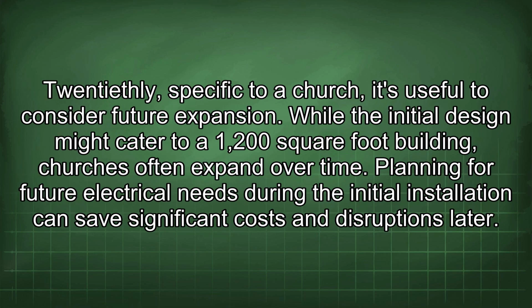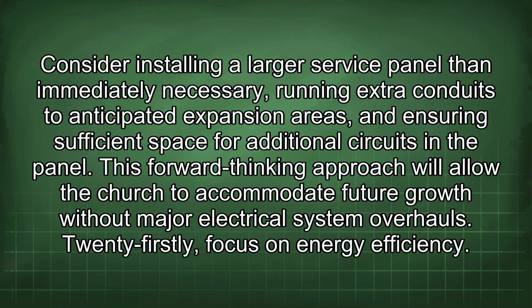20thly, specific to a church, it's useful to consider future expansion. While the initial design might cater to a 1,200 square foot building, churches often expand over time. Planning for future electrical needs during the initial installation can save significant costs and disruptions later. Consider installing a larger service panel than immediately necessary, running extra conduits to anticipated expansion areas, and ensuring sufficient space for additional circuits in the panel. This forward-thinking approach will allow the church to accommodate future growth without major electrical system overhauls.